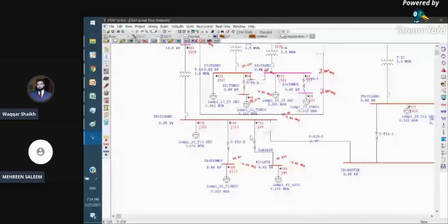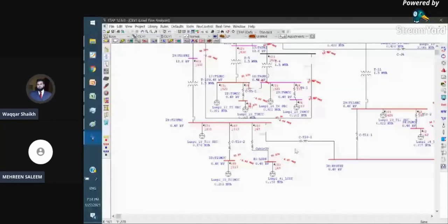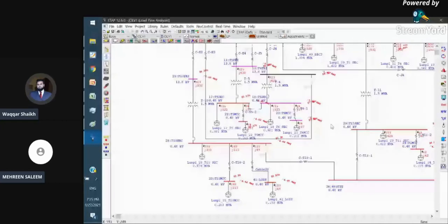So are we going to change all the cable sizes in this network? Of course, this is not a practical solution, that if you have an under voltage problem you increase the cable sizes throughout the network, especially for an existing installation. So what can be the most optimal solution to handle this problem? One of the best ways is to change the transformer taps. This is one of the most recommended solutions to optimize network under voltage problems. So let us see how we can apply this feature in the ETAP software.